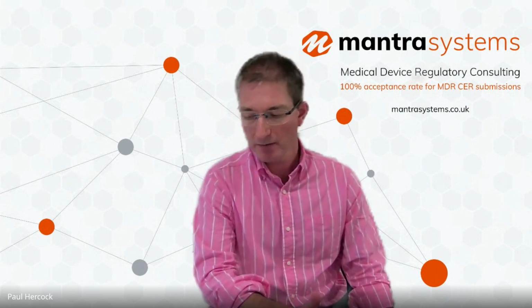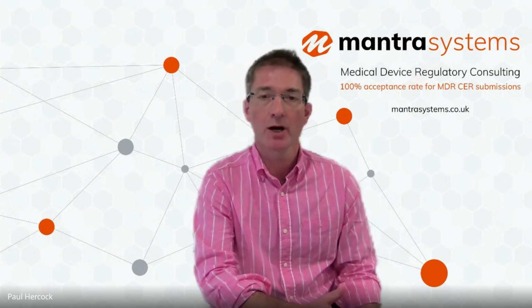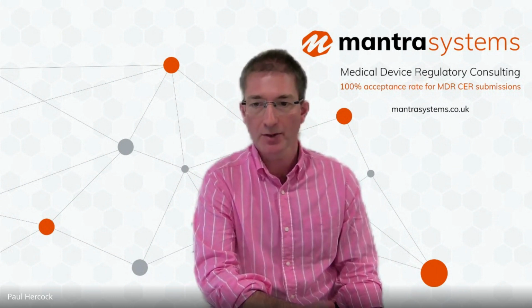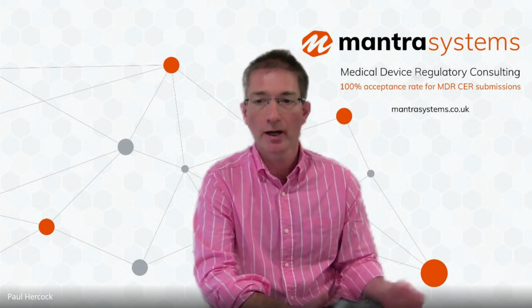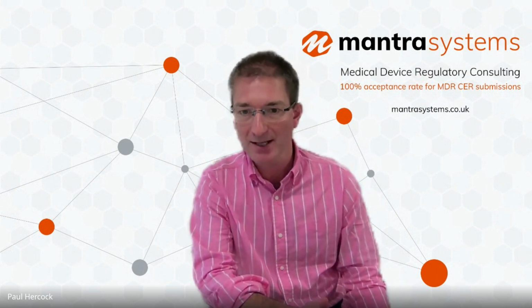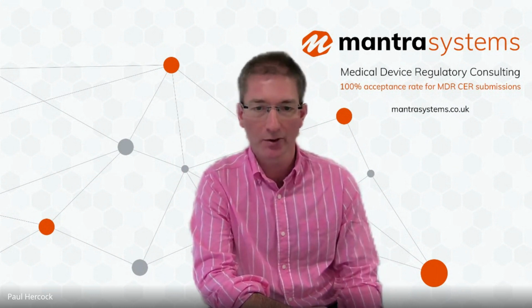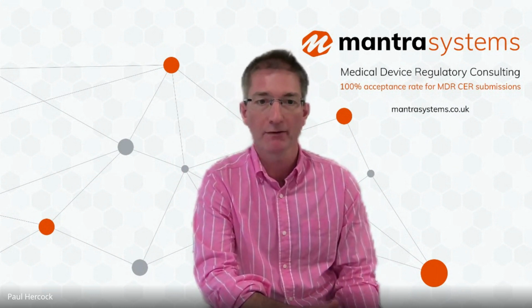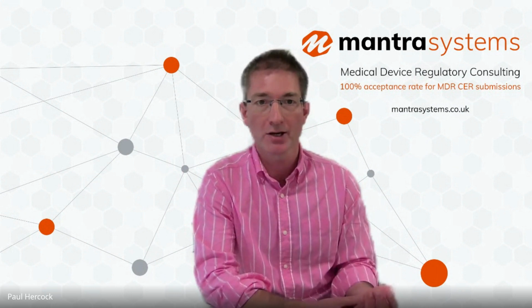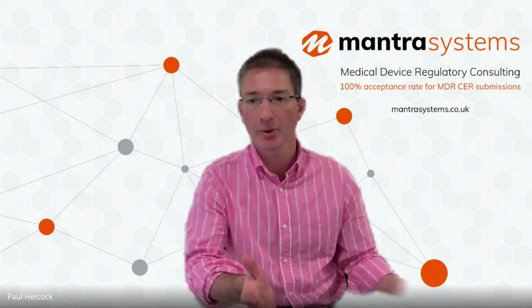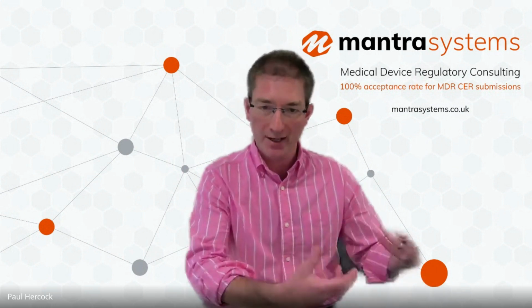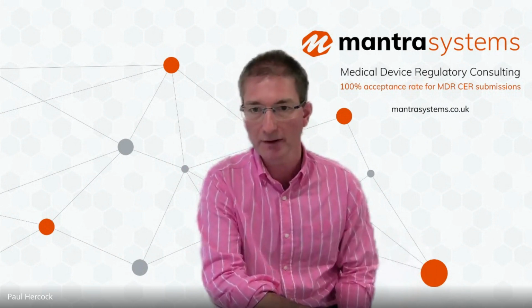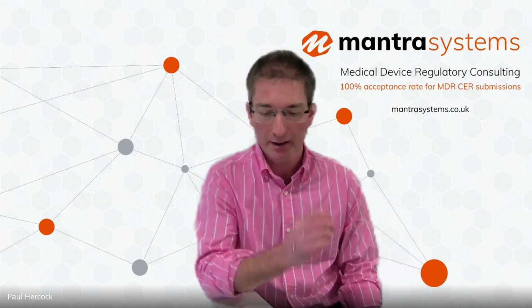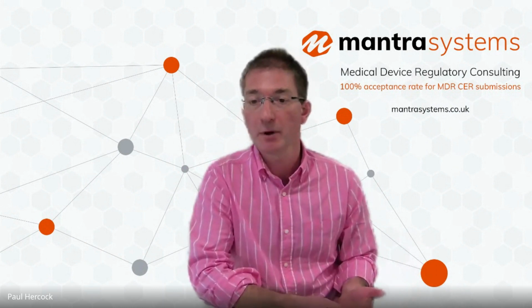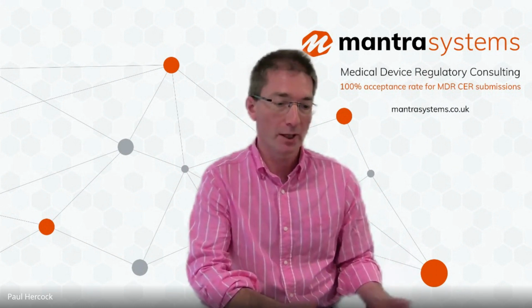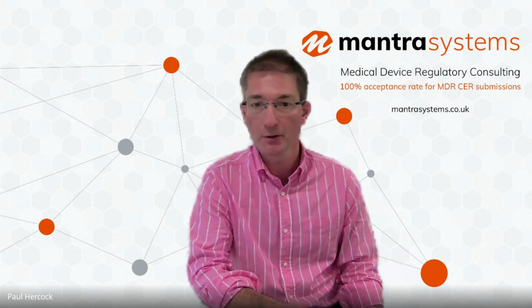The reason for that is that if you don't account for all the excluded sources, then you're not able to demonstrate that you haven't been selective in the ones that you've included. In other words, have you just picked those that make life easier or show your device in a better light? I'm not suggesting anybody on this call would actually do that, but that's the thought process of a reviewer. So you need a good, effective, efficient process for recording and justifying your exclusions.